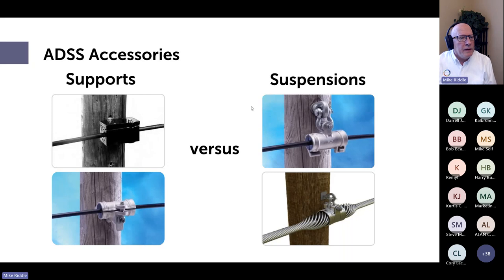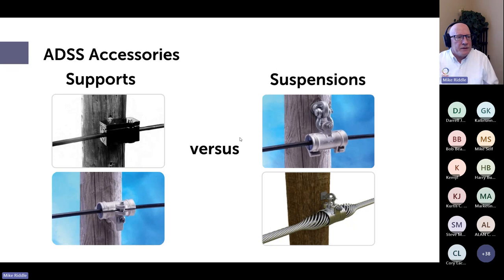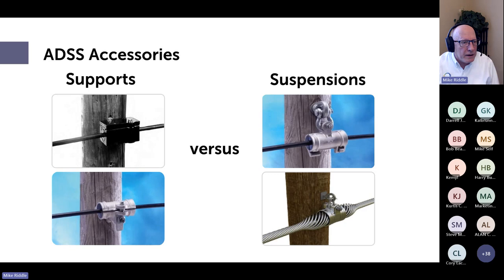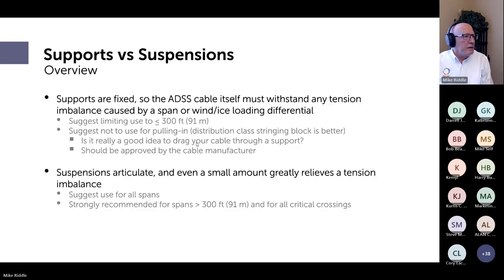For example, if one span is 1,000 feet and the adjacent span is 100 feet, you have a significant tension imbalance — more vertical load from the cable plus greater tension under wind and ice conditions. A suspension only needs to move a little bit to equalize that tension. With a fixed support, the cable must endure that imbalance with no relief — nothing good can come from that. I suggest limiting supports to spans of 300 feet or less.